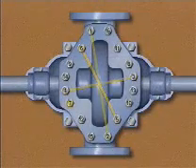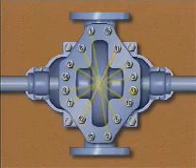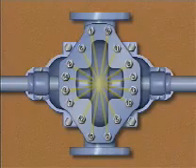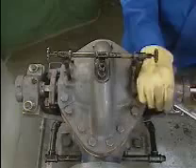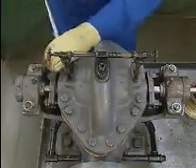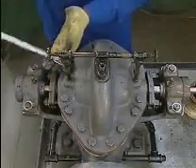Like other tightening sequences, it is a crossing pattern. The mechanic follows the pattern, crossing back and forth until all the bolts are tightened to the required torque value. He will repeat this pattern several times, gradually increasing the tightening pressure in several stages. If this tightening process is not followed, the sealing surfaces could warp, or the gasket could be improperly compressed.